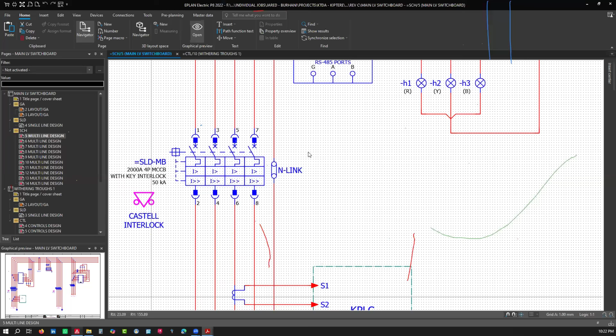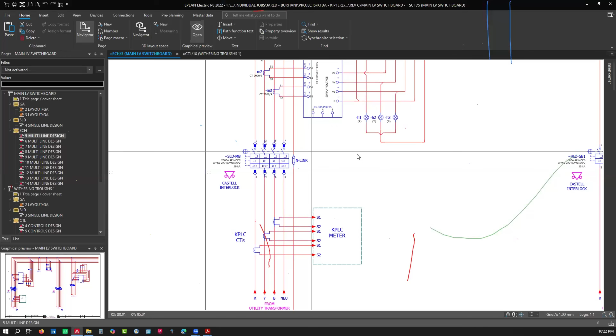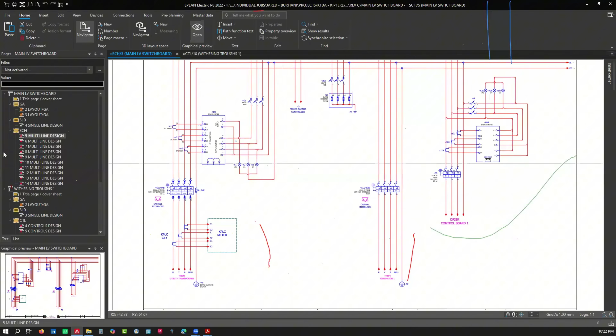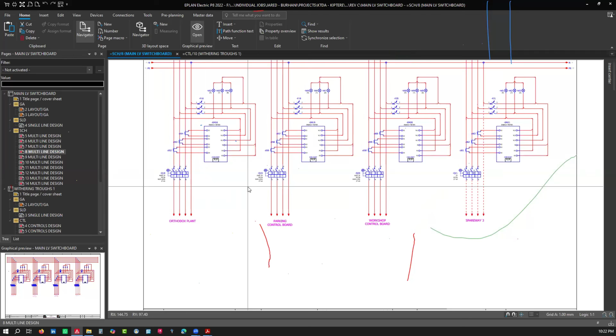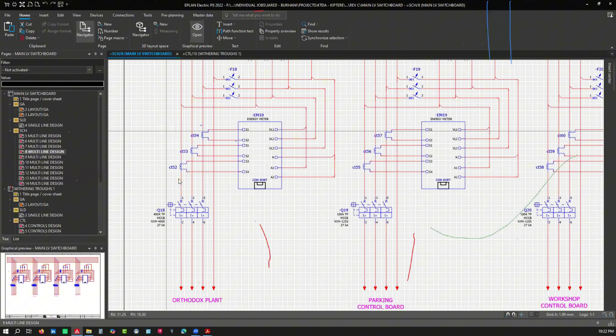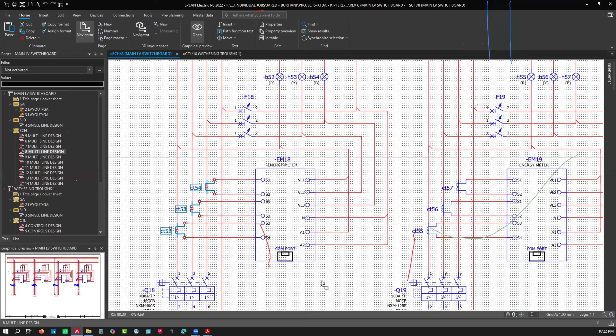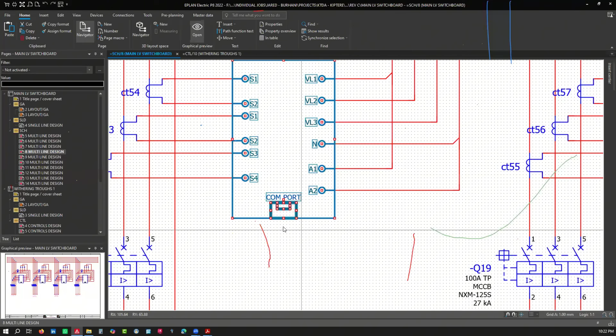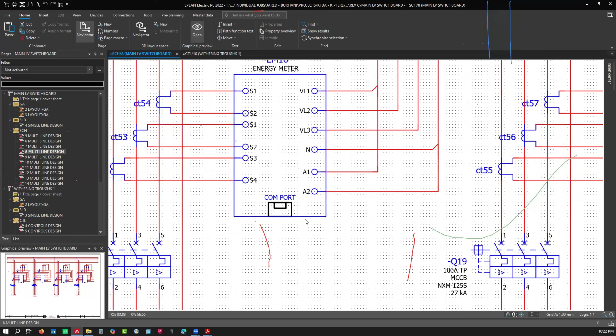If you have controls, let's say a changeover system, you need to develop a control for that changeover. All multi-lines need to provide a clear connection of all the components used for that system, so that if you're connecting to a specific device, someone will know - I have CTs coming into an energy meter. The energy meter has a communication port, meaning you can do a daisy chain to collect data for BMS, building management systems.